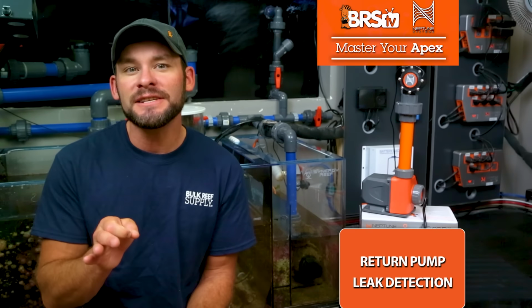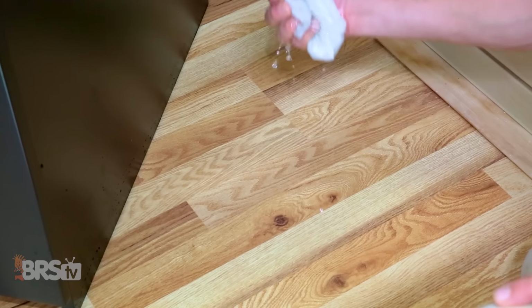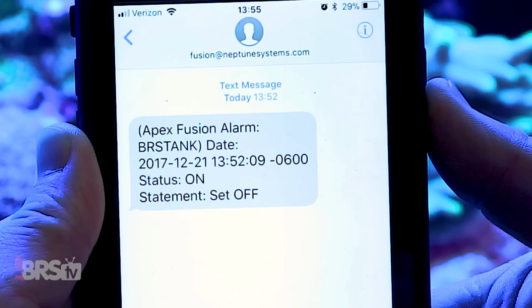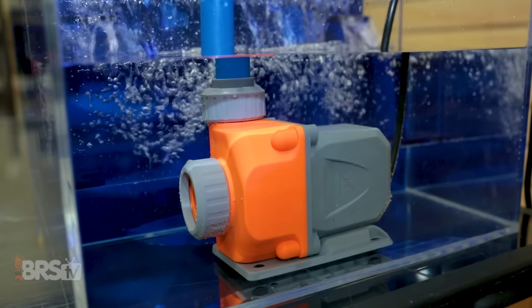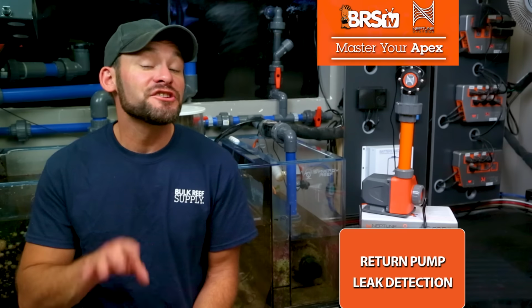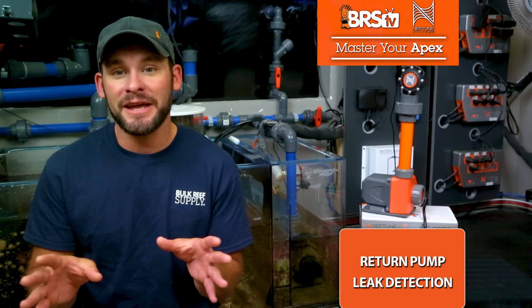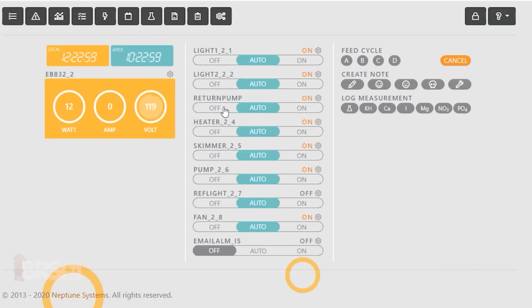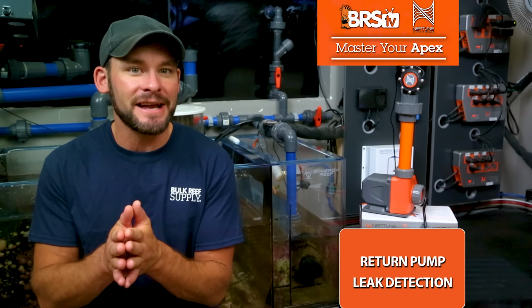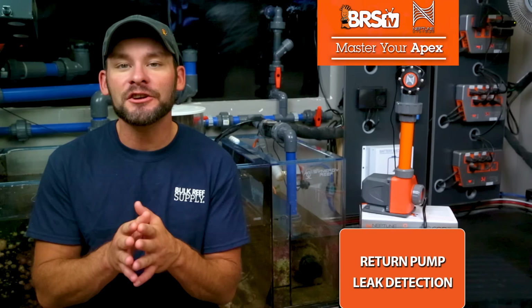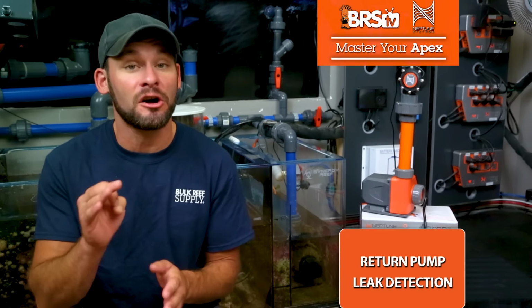and you can do the same for your sensor names. But now if there is water on the floor or where it's not supposed to be, you'll get an email alert, and at the same time, your return pump will automatically turn off. Alternatively, you could just rely on the notification to let you know that there is a leak and then use the Fusion app to manually toggle the pump on or off. In either case, the notification is actually the most important component to solving this issue.